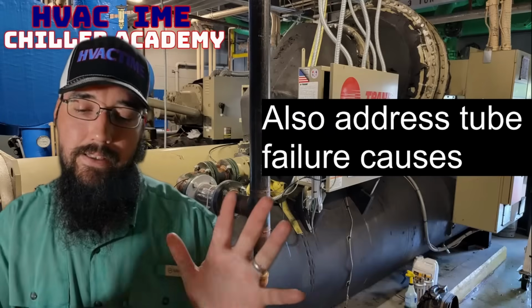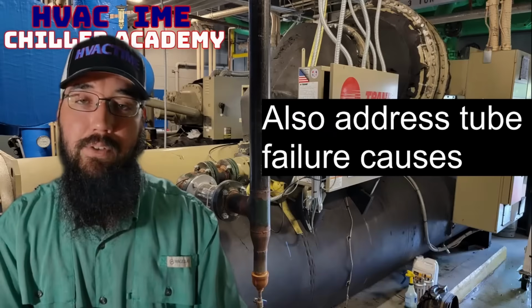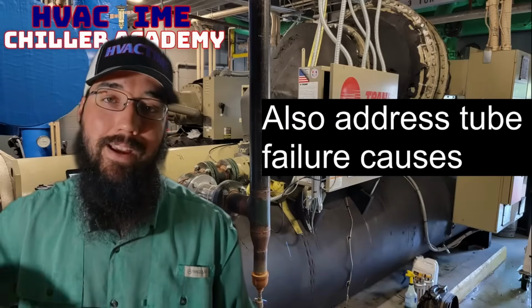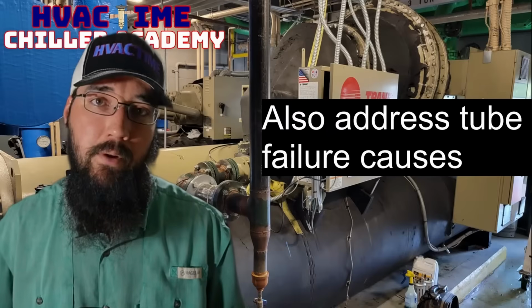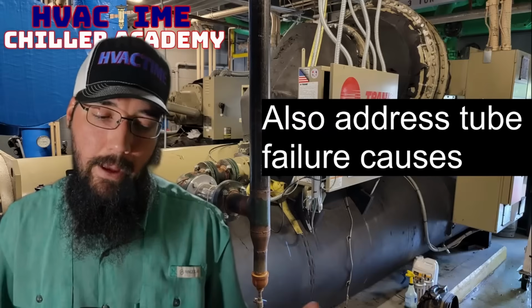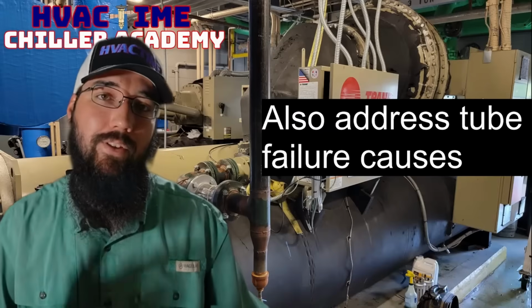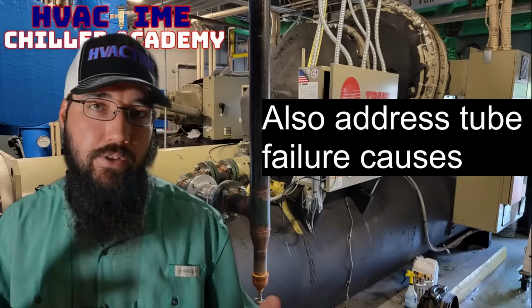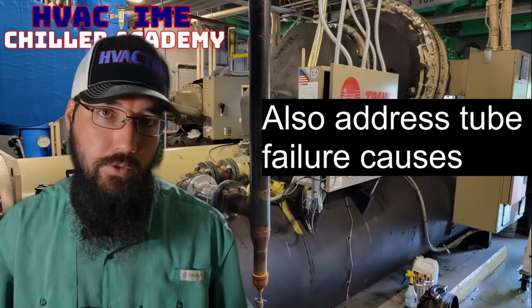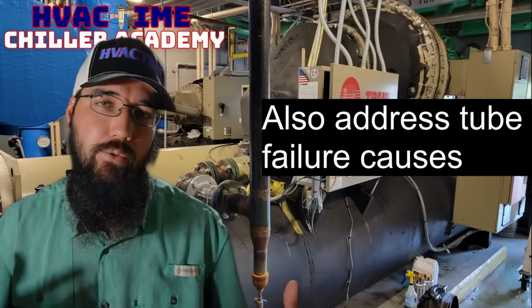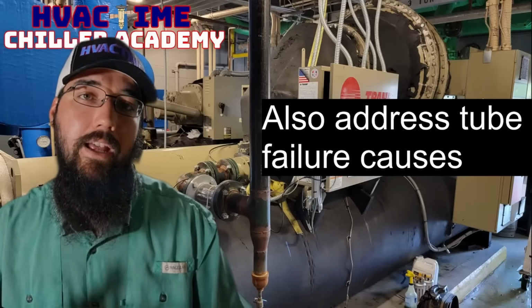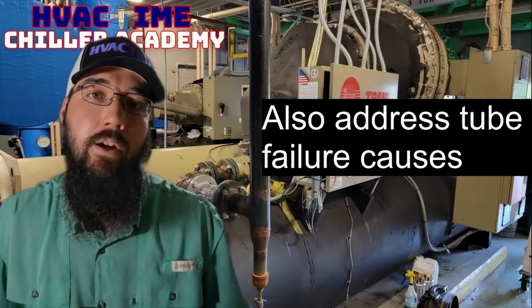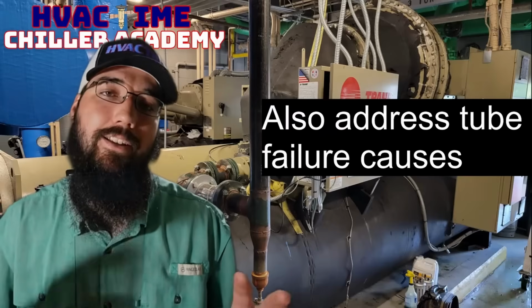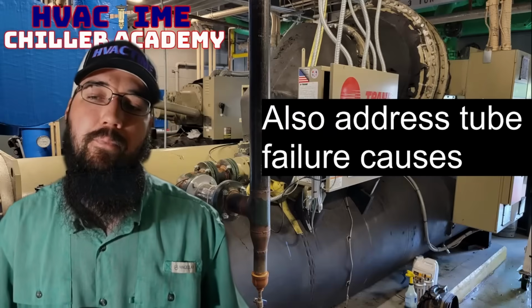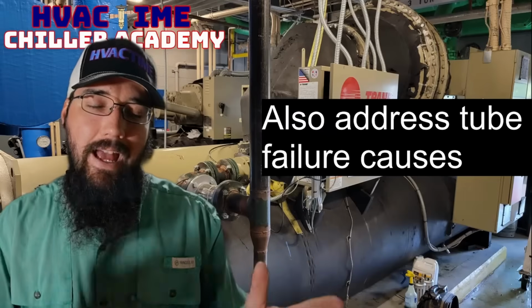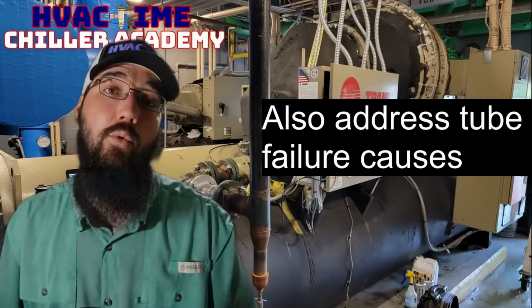There's a property that we've worked at where some of the pump strainers had collapsed and disintegrated into a bunch of different pieces and made their way through the piping network. Most of the time, our pumps are going to be pushing directly into our chiller. What happened in this case is those little fragments got into the condenser specifically, and they were big enough and sharp enough that as they went through the condenser, it just started punching holes on its way through. Technically it was two different chillers, and it led to having to plug a bunch of those tubes until eventually we had exceeded the amount we could plug and still have any reasonable amount of function, in addition to just trying to stop the leaks in general. So having debris that is able to puncture a tube is another way to have a tube failure.